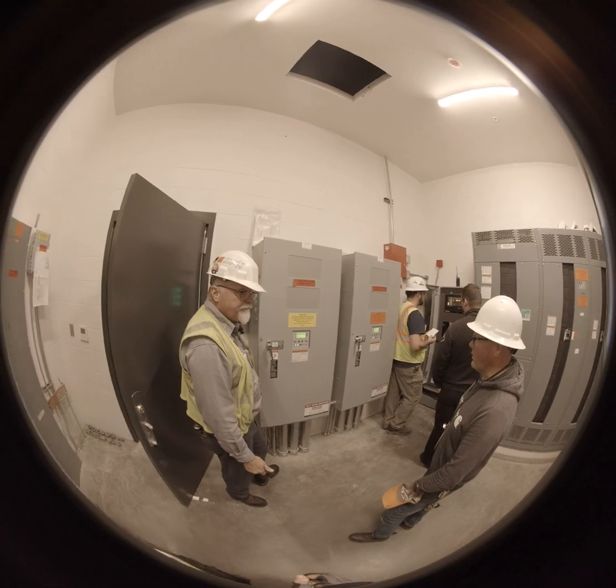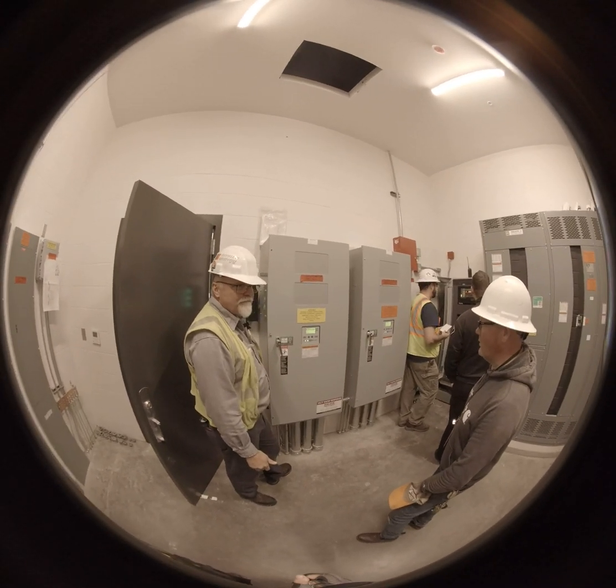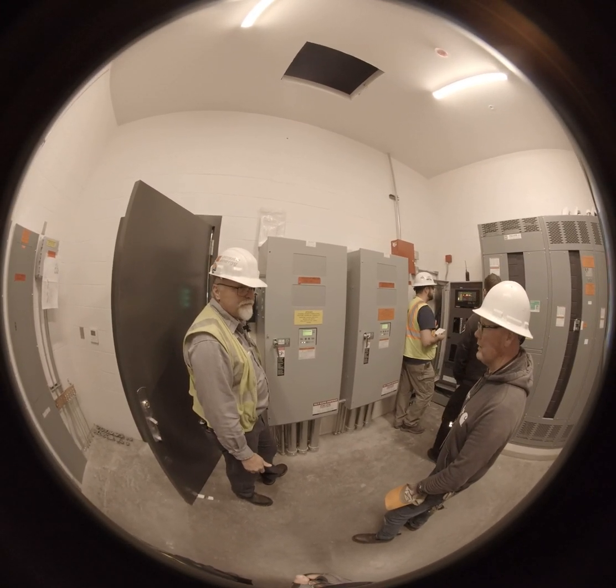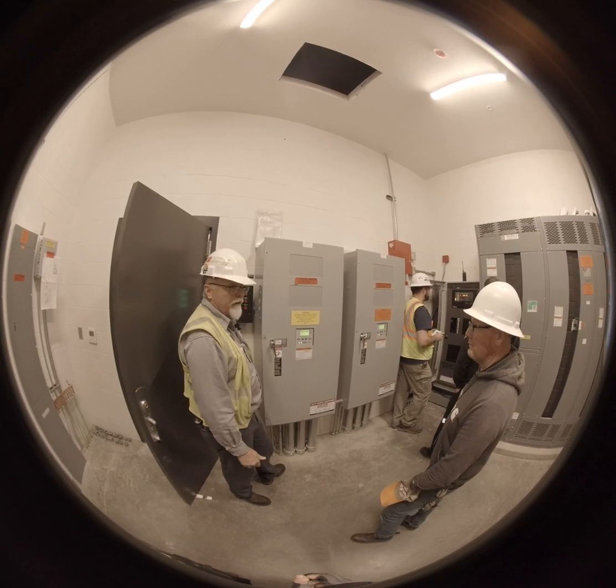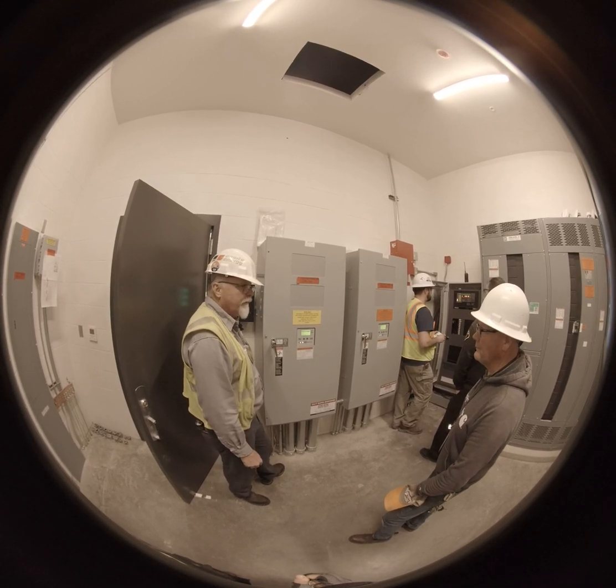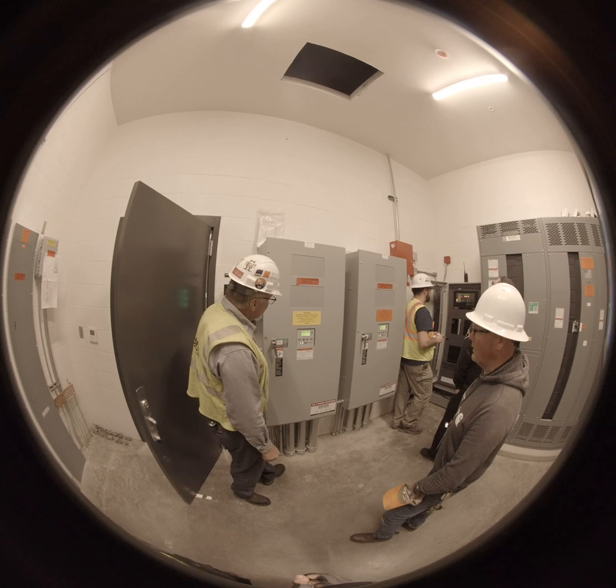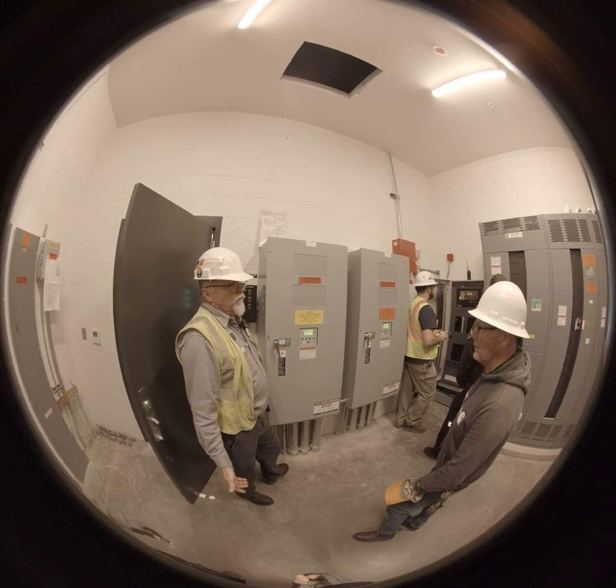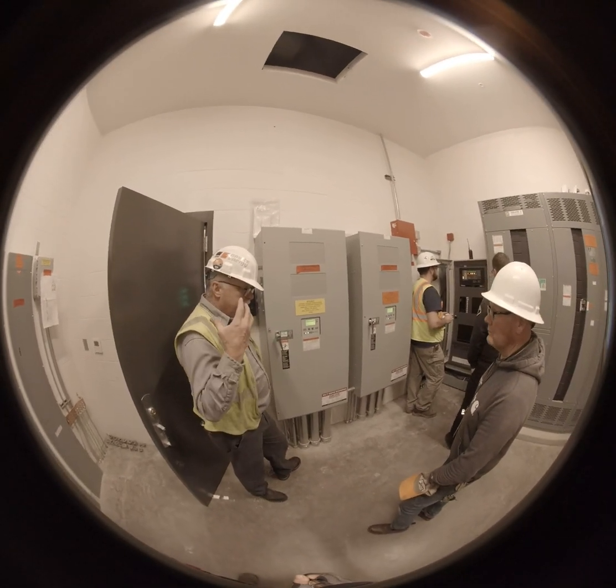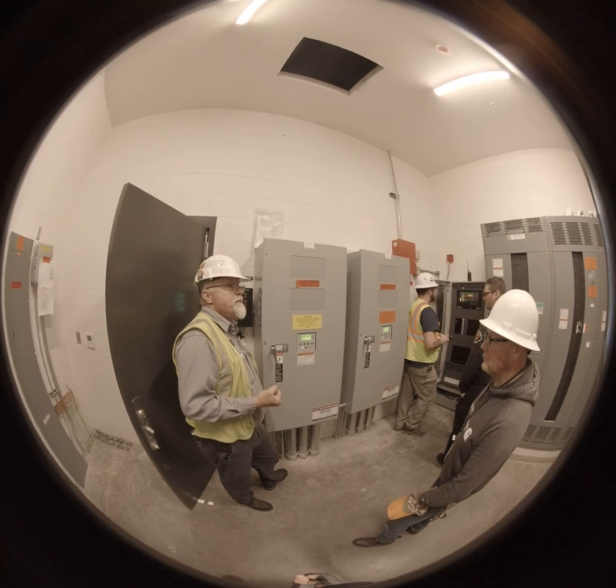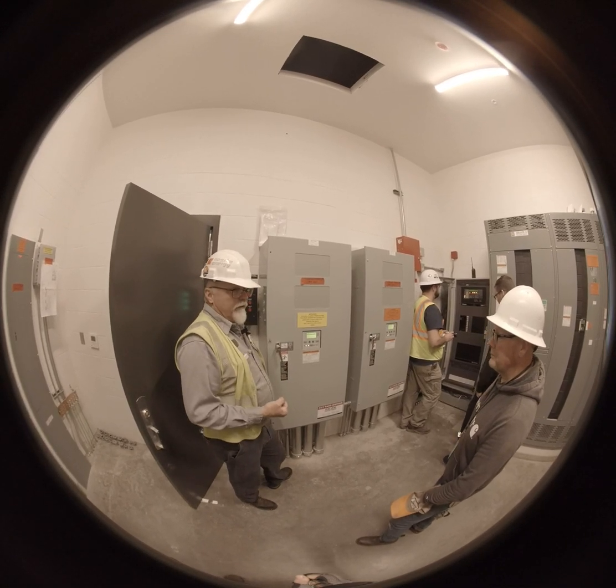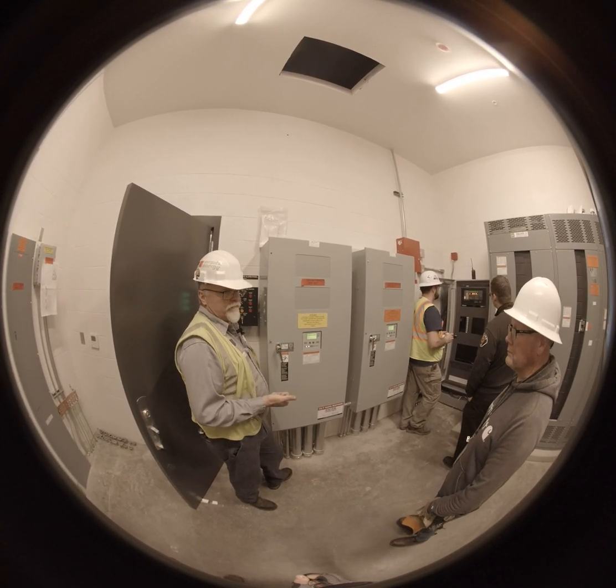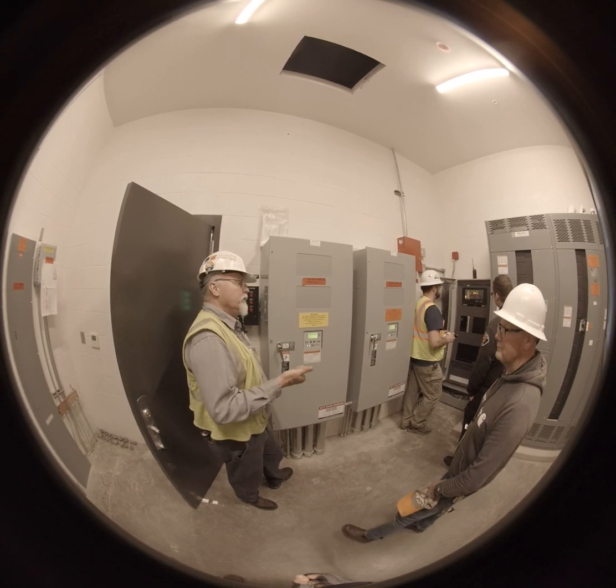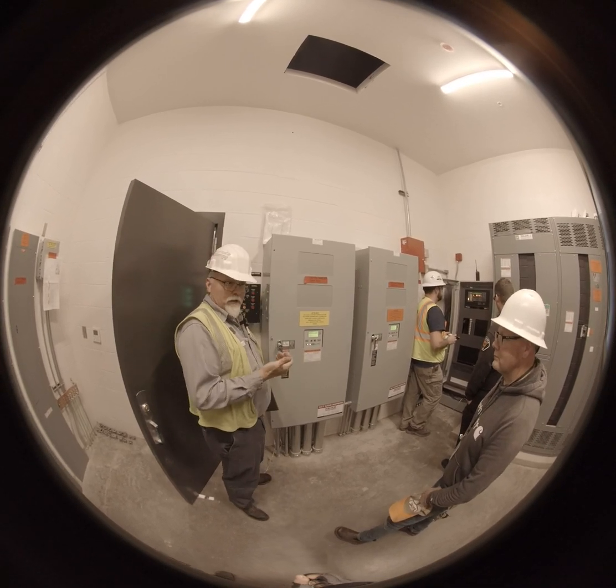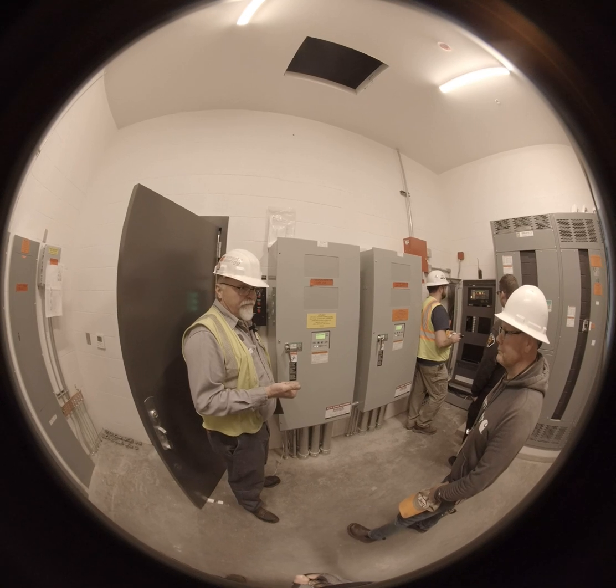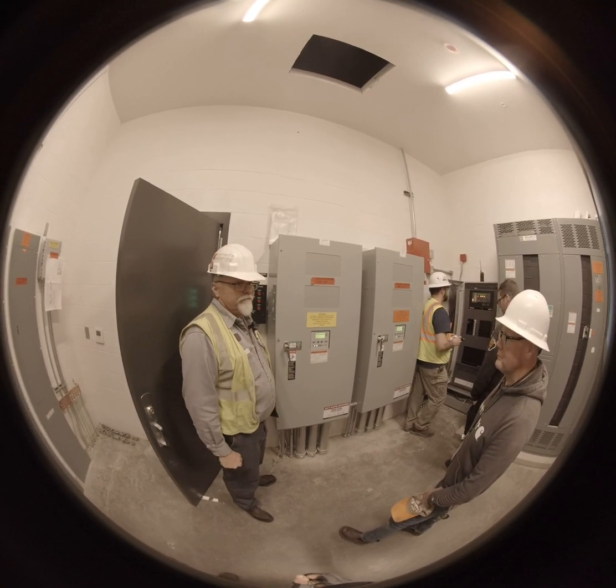I usually just program them once a month for 20 minutes. Mm-hmm. Yep. With or without a load? Without. Without a load, yep. Now, they do the load bank test once a year. The factory recommended maximum time duration between exercises, I guess you'd call it, is a month, 28 days. They do not want you going beyond 28 days.